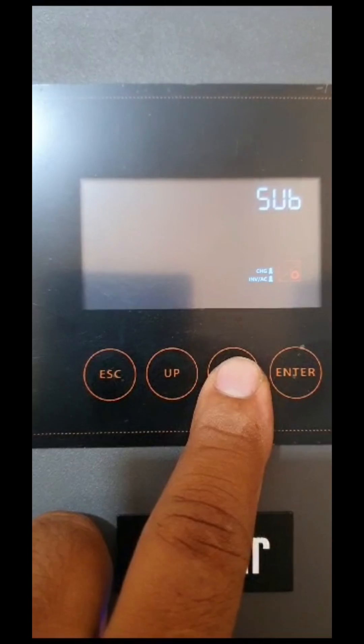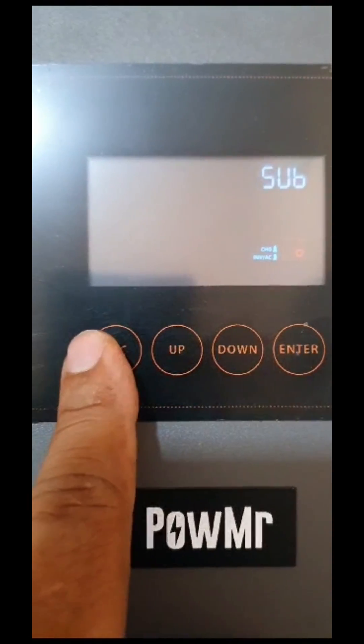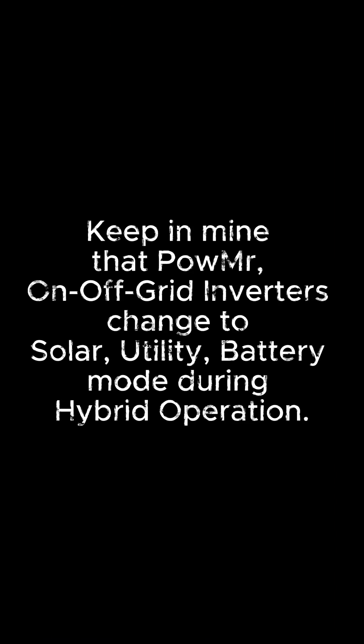This issue is not mentioned in the manual or on the website. Even the salesperson was unable to respond without checking with the engineers. So keep in mind that PowMr on-off-grid inverters change to solar, utility, battery mode during hybrid operation.